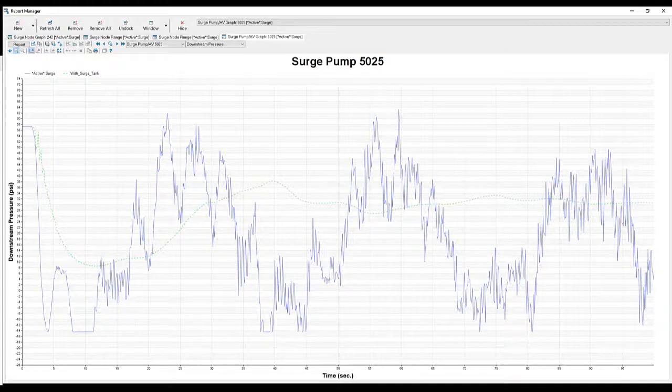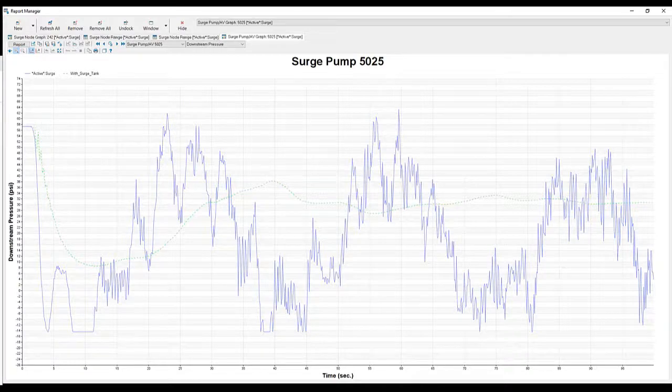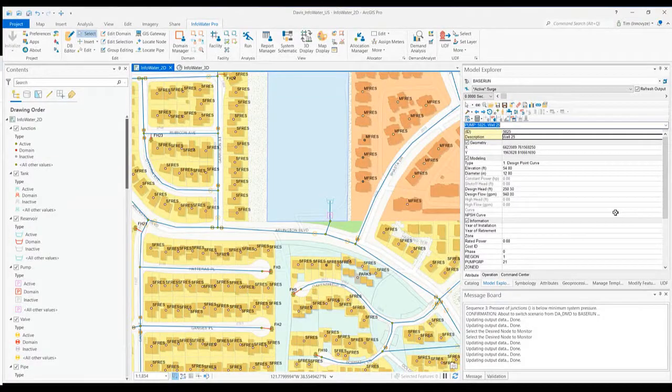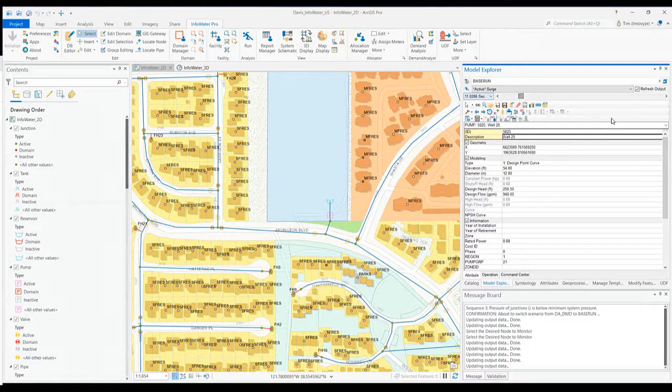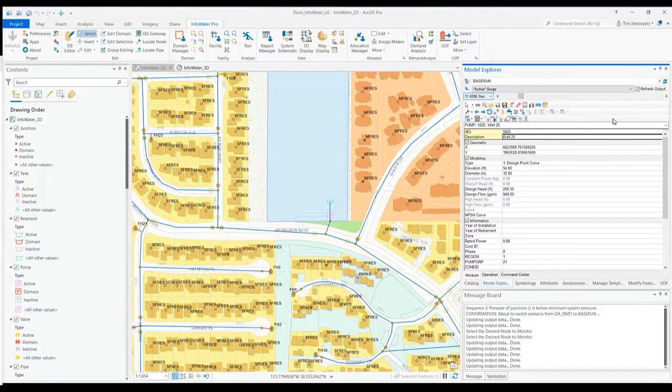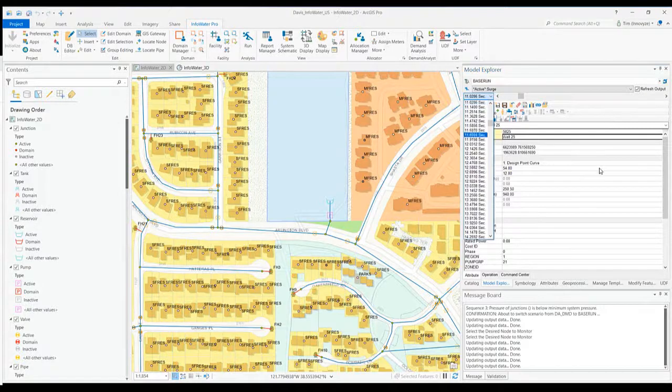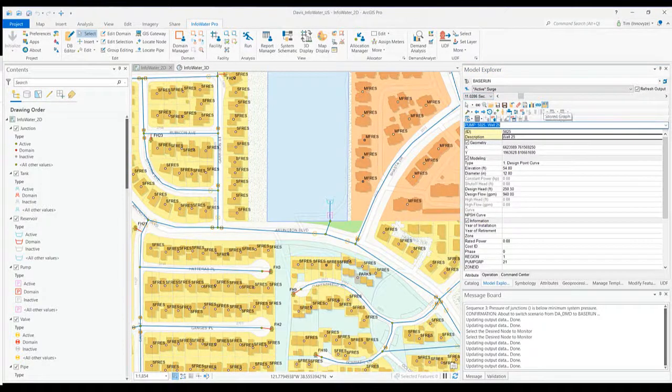One of the big things with surge analysis is normally your InfoWater Pro hydraulic run is done in minutes, hours, days. For this, you're really looking at a very quick time step. If you were to color code your map looking for those areas that have very minimum pressure, you can review your results. The time step is seconds instead of longer minutes, hours, or days.